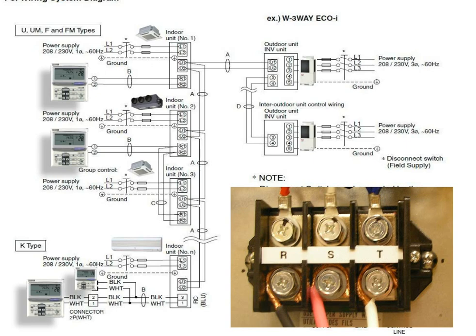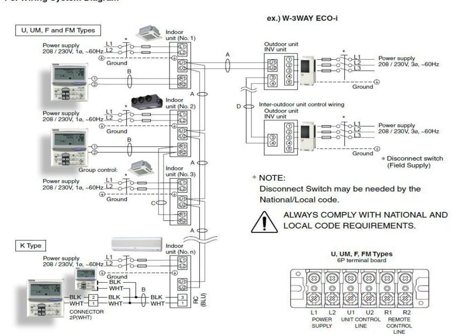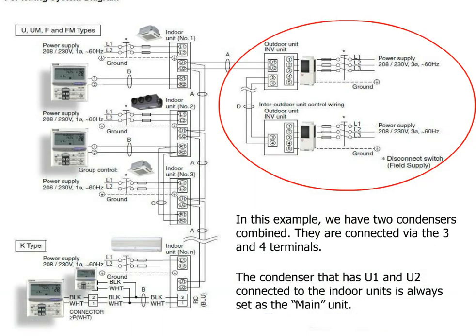If one leg of your 3-phase power supply has a higher voltage reading than the other 2, this leg should always be landed on L3, which is labeled T, at the high voltage terminal block in the condenser. This is commonly called a wild or stinger leg. In this example, we have 2 condensers combined. They are connected via the 3 and 4 terminals on the condenser.